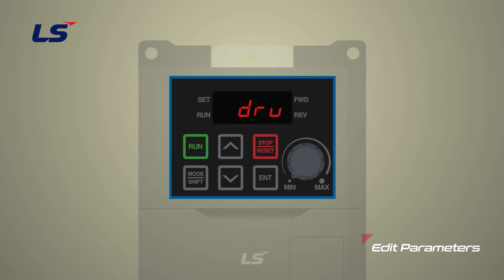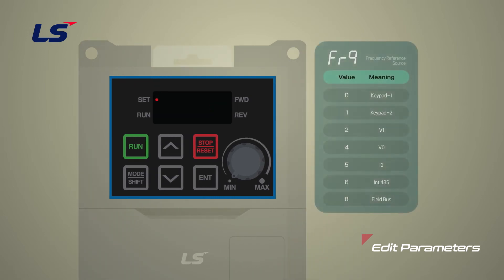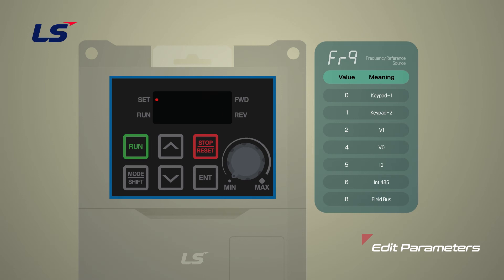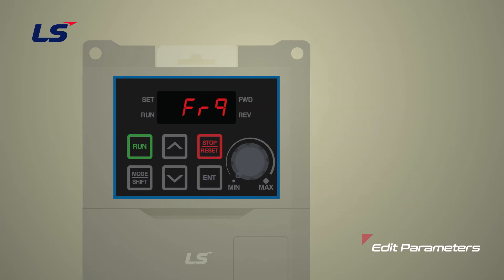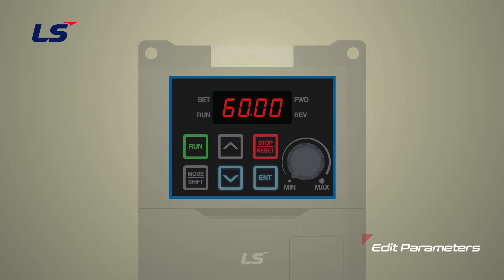Next, move to the frequency parameter by pressing the up arrow key once to edit the frequency reference source. Press the enter key to confirm the value. When entering the edit screen, the previously set value blinks. Here, the meanings of numbers are as shown in the table on the screen. That is, if it is 0, it means that it is set to keypad 1, and it means you can set the frequency by the keypad on the initial screen. We will not change this parameter. You can return to the initial screen at once by pressing any two keys at the same time after pressing the enter key to exit.